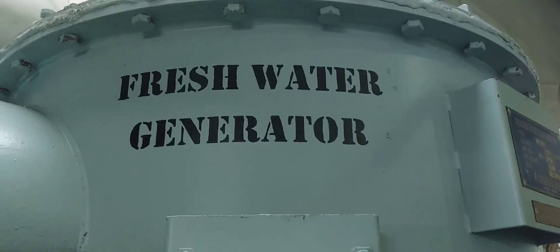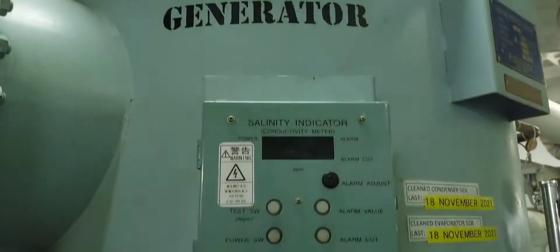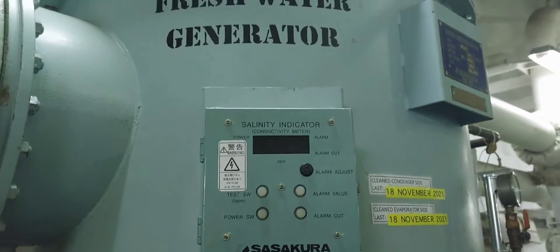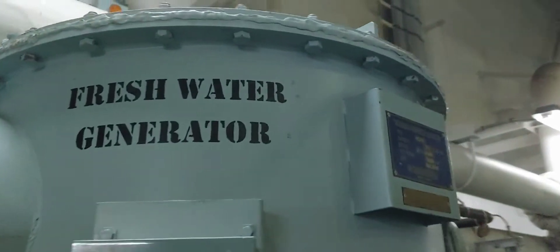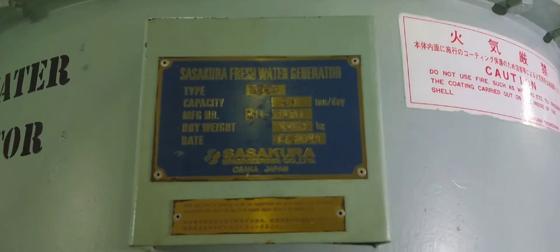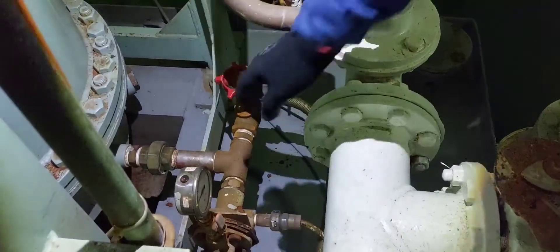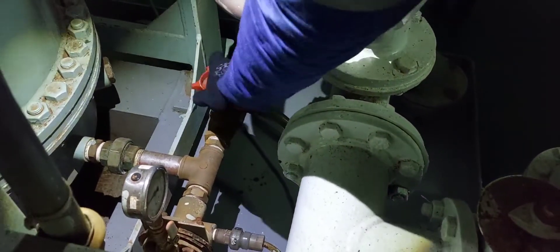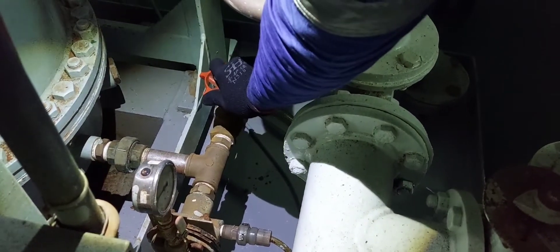Procedure for starting: on board, this is our fresh water generator. The maker is Sasakura Engineering Company Limited, model Kilo Eco 30. This fresh water generator has a capacity of 30 tons per day. Prior to starting, you have to secure some valves. This is the blowdown valve for draining the heater side — you need to close it before starting.